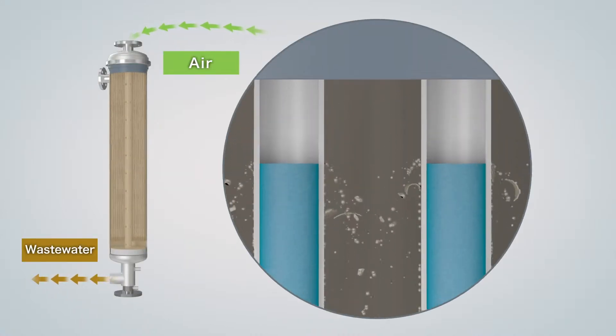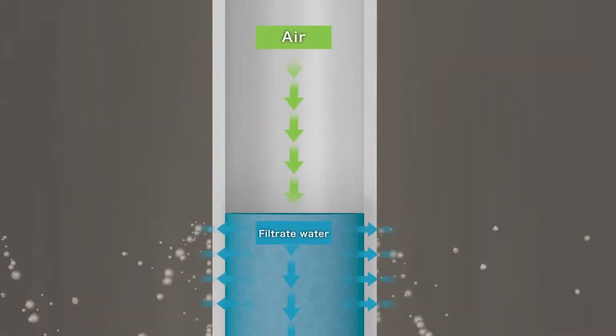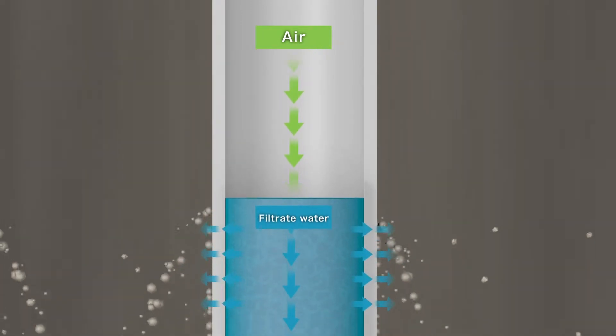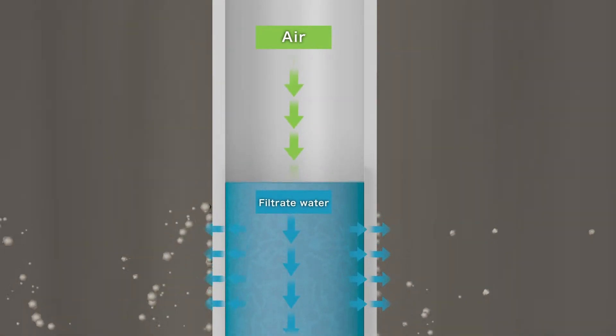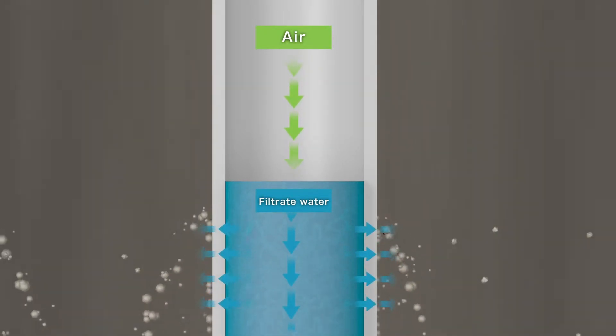The attached particles caused by filtration are removed from the module using physical cleaning. In the air backwash process, compressed air is supplied from the filtrate water side of the module. And by applying pressure to the inside of the hollow fiber membrane, the surface particles are detached.